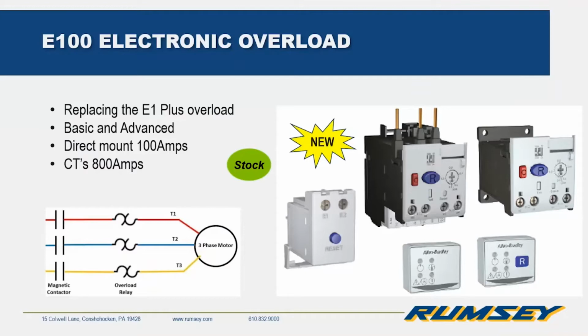The advanced version gives you availability to some extra add-on modules. With the advanced version, you can use an electronic remote reset, the ground fault module, and there's also a jam module that can be used with it. It offers automatic reset as well. Also, in the picture on the bottom, there's a panel mount unit that can be used with the advanced as well. It has some LEDs on it that give you the status of the overload, and you can also reset it remotely with that panel mount unit. The direct mount overloads go up to 100 amps. If you need something larger, all the way up to 800 amps, we can achieve that, but we need to use current transformers with it.